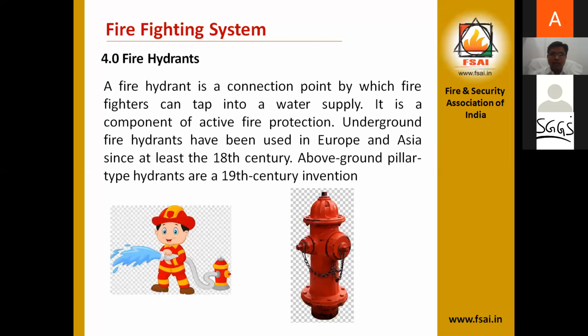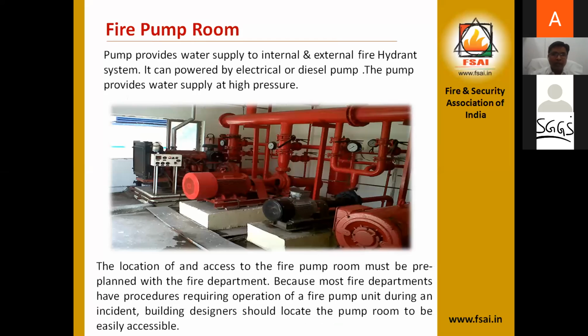The next is the pump room. The pump provides water supply to the internal and external fire hydrant systems. The role of the pump room is very important because it supplies water to the hydrants and sprinklers. It can be powered by an electric or diesel pump. The pump provides water supply at high pressure. The location and access of this pump room should be pre-planned with the firefighting department, because the fire norms of every city are different, and most fire departments have procedures requiring operation of the fire pump.